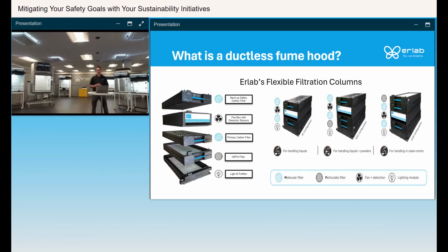Above that, you have the fan box. That is what is driving the air away from the end user and up into the filtration column. And that is also where the solvent detector and/or acid detector is located. And then above that is the backup carbon filter for safety redundancy.